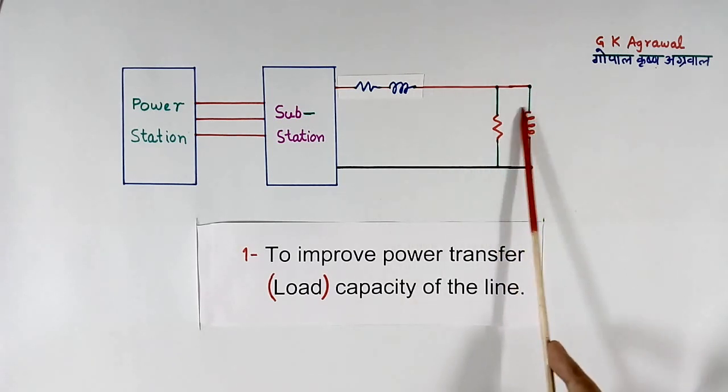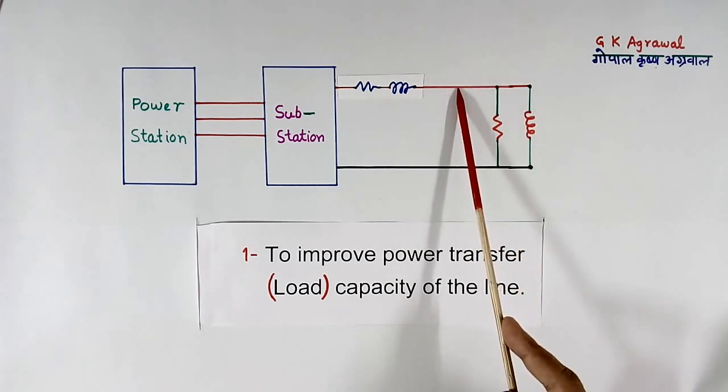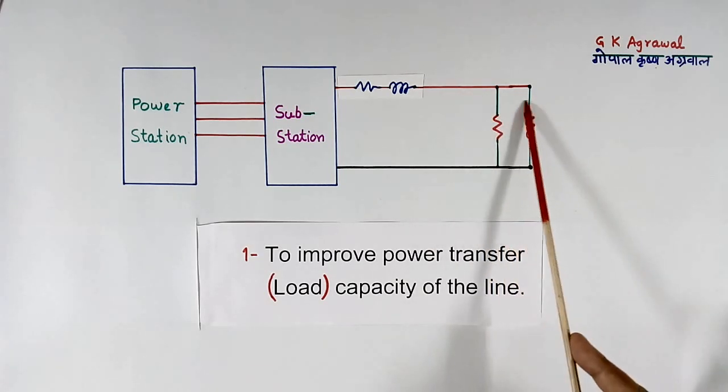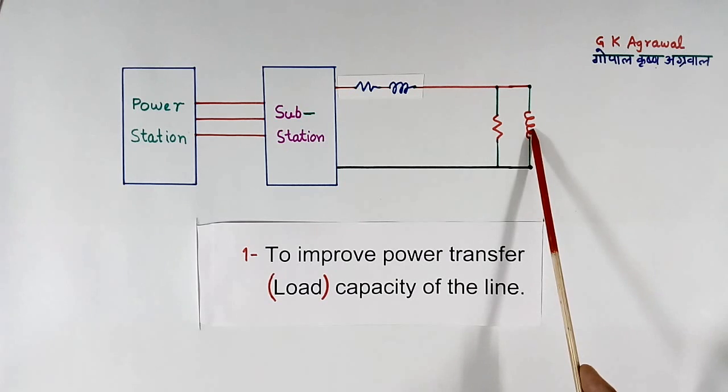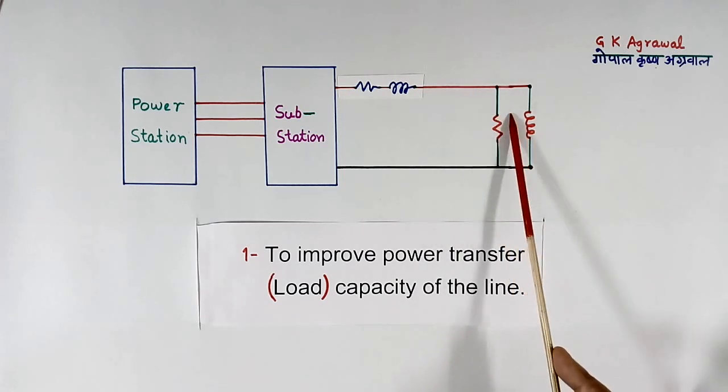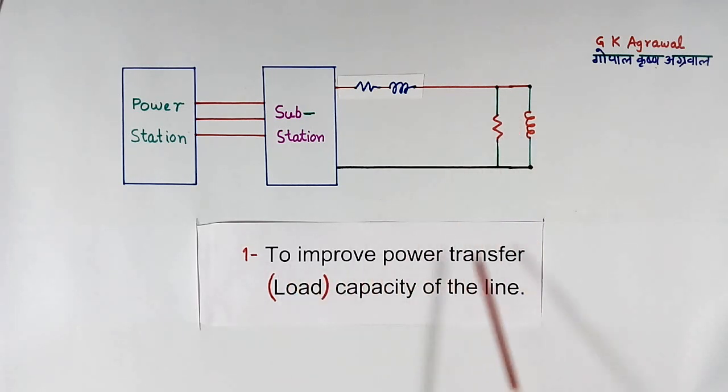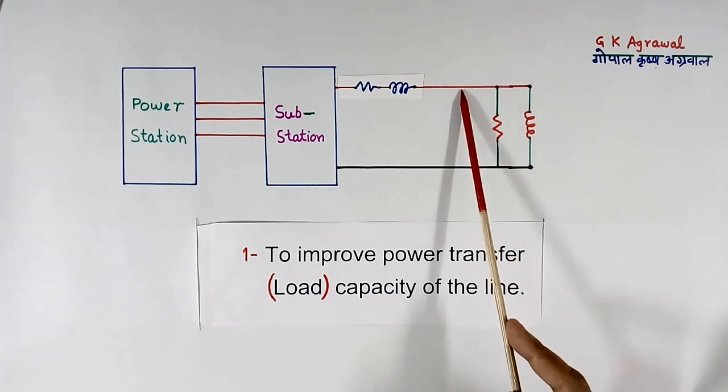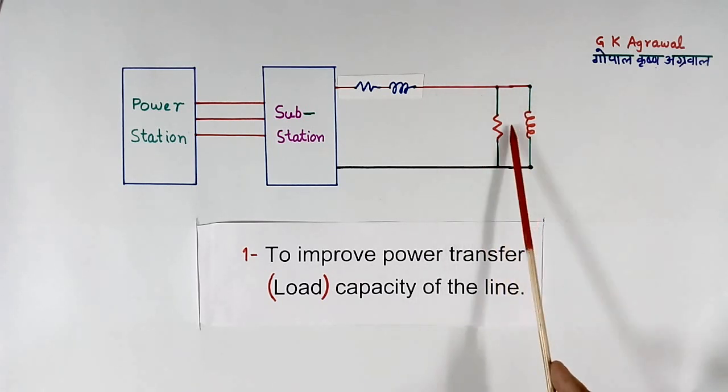If we remove this somehow, then here current will reduce. Then we can connect more load because this current is not there. So additional load can be connected. That is what it is called, to improve the power transfer capacity. Because by improving power factor, we can reduce the current here, so we can connect more load.